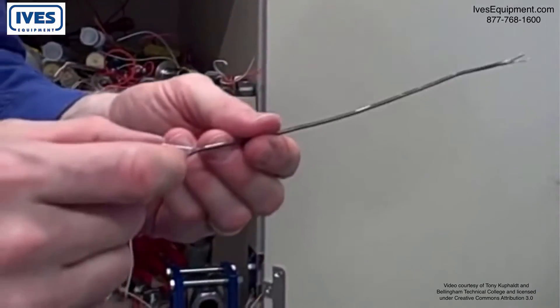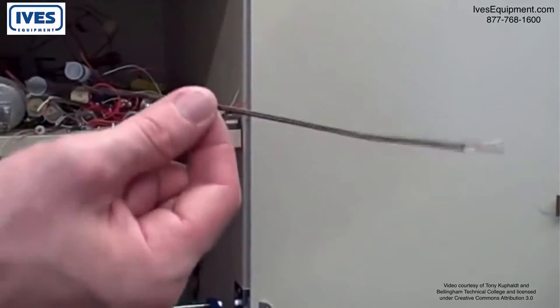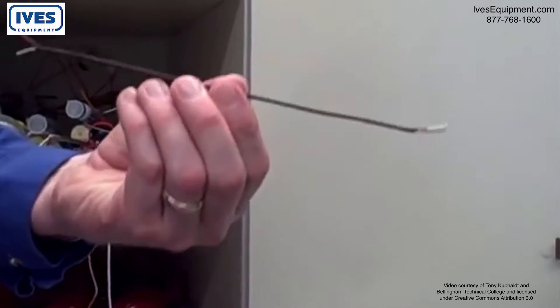We could then connect the other two ends to a thermocouple instrument and have ourselves a working sensor. This is how simple a thermocouple can be. It's nothing more than a pair of dissimilar metals of specific type joined together to make a junction.